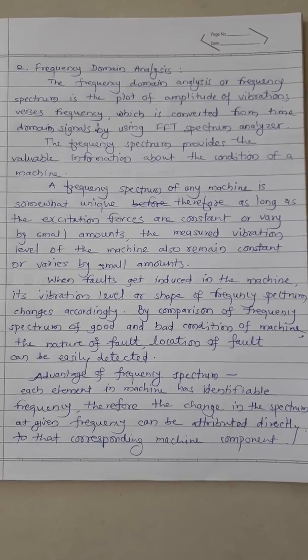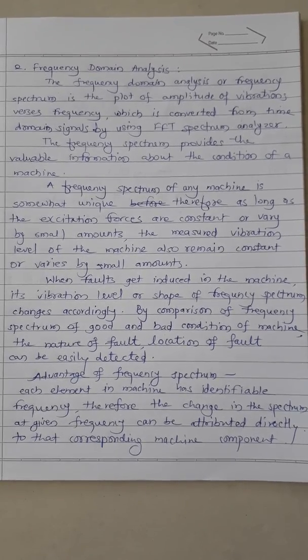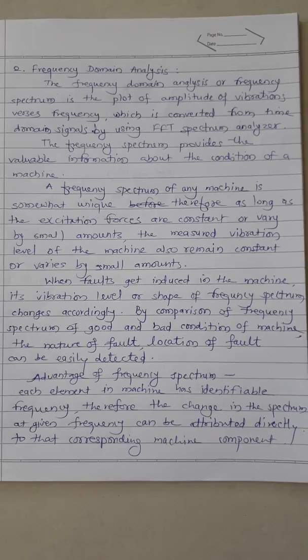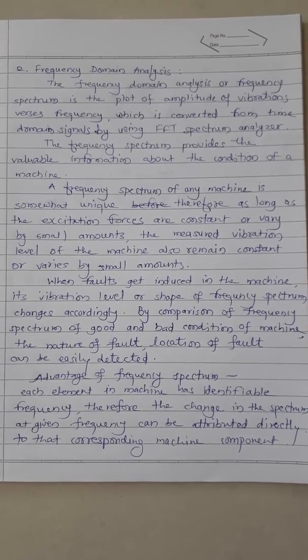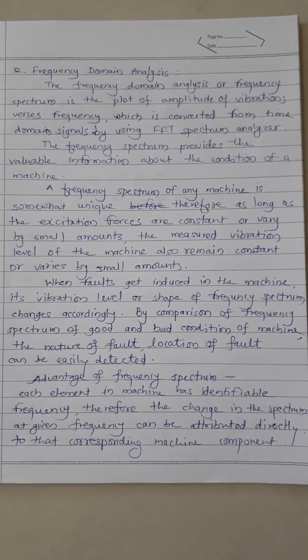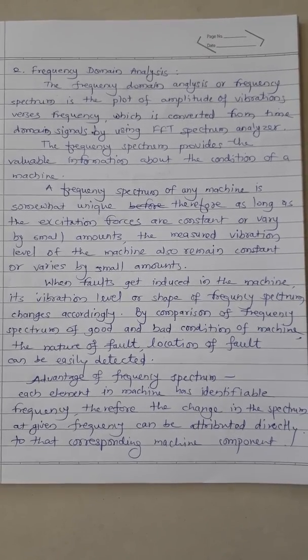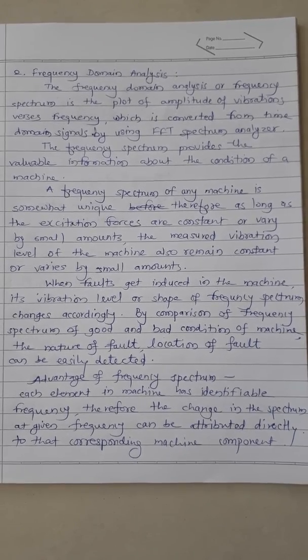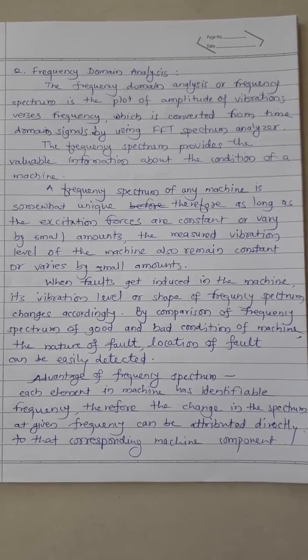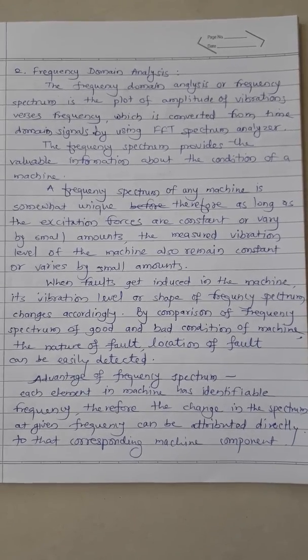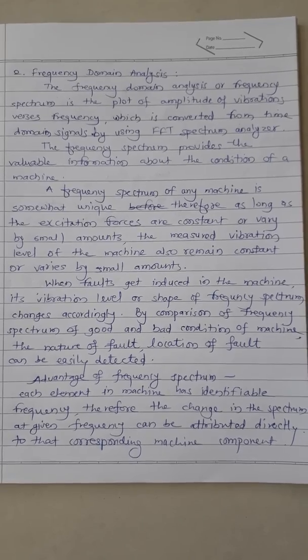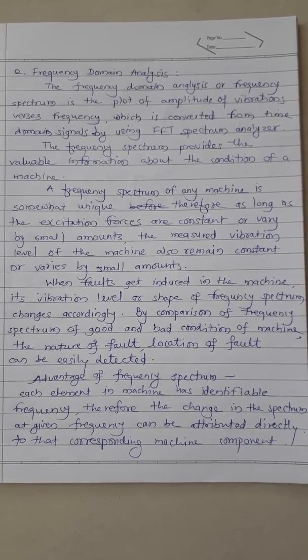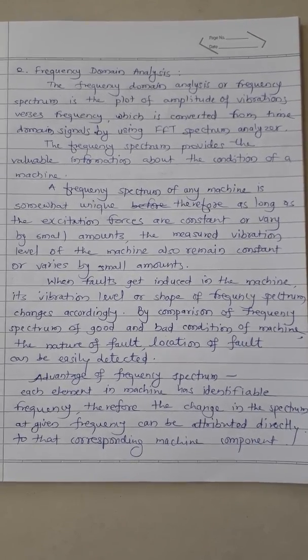When the machine parts develop faults, the vibration level changes and the frequency spectrum changes accordingly. By comparison of frequency spectrum of good and bad condition of machine, the nature of fault can be found out and the location of fault can be detected.